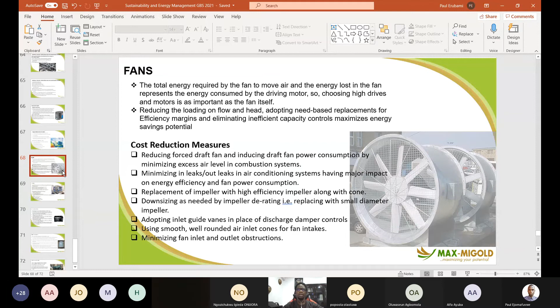Downsizing as needed by impeller derating, all right? So replacing with a smaller diameter impeller. Adopting inlet guide vanes in place of discharge damper controls. Using smooth, well-rounded air inlet cones for fan intakes, minimizing fan inlet and outlet obstructions.